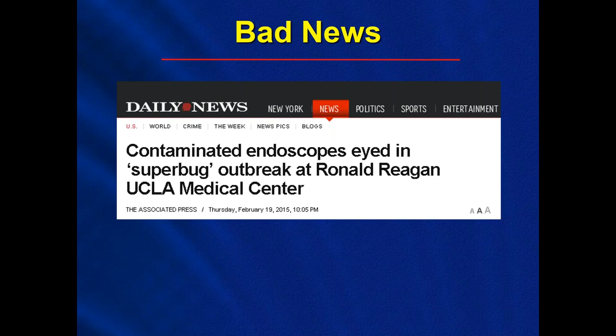Now here's the scope that was the culprit in that whole thing. It's the ERCP duodenoscope. This is the one that was involved in the event in California in 2015. The problem with this scope that they noted was that if you look over on the right here, this elevator mechanism, this is a movable mechanism that is attached on either side. And it moves up and down to allow the passage of guide wires or biopsy devices or brushes, things like that. The problem they discovered was that because it's mounted on either side, it's very difficult to get in there and clean those areas where it's pinned on either side. That's where the contamination they determined was coming from inadequate cleaning. So a lot of manufacturers revamped the design of their scopes and also came out with new guidelines for the cleaning and the reprocessing of the scopes. That also had an impact on other flexible scopes without the elevators with regards to cleaning processes also.